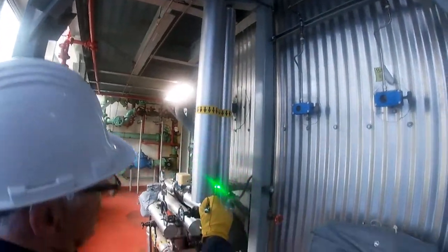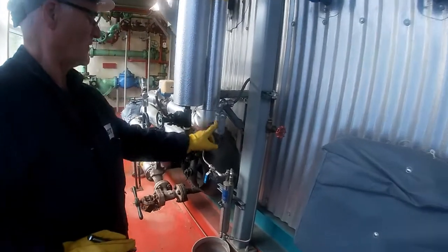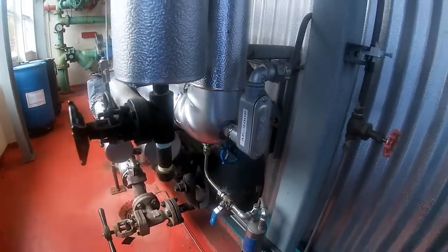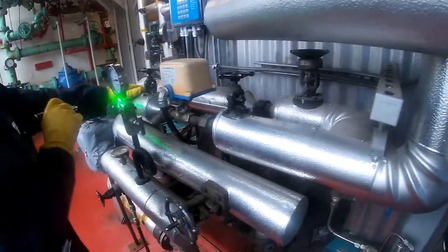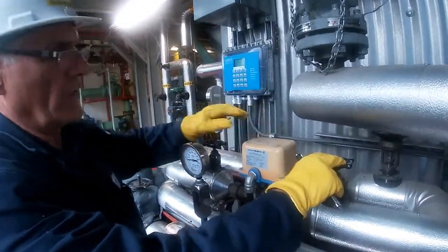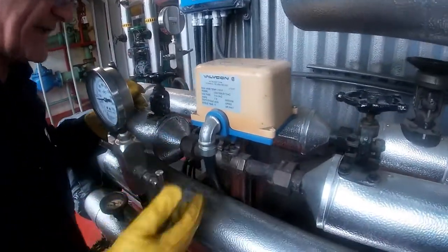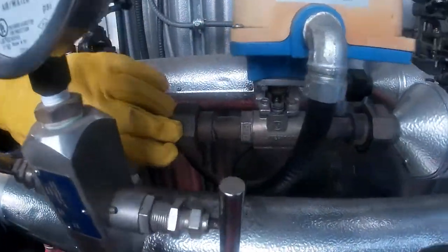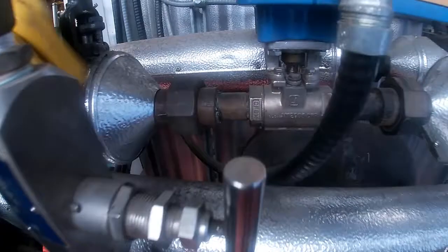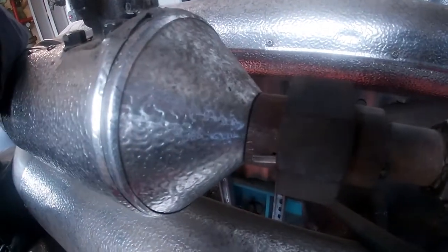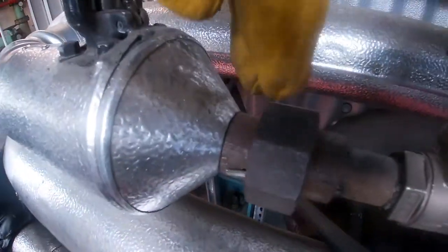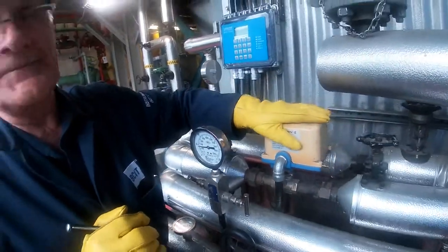The blowdown comes to this conductivity sensor, which measures the conductivity of the water that's coming out of the blowdown. From there, we go through these 2 hand valves to this control valve, and in fact, it's hard to see, but there's actually an orifice in here which limits the amount of flow. And that little tiny tab that's sticking out of the end of that union actually holds on to the little orifice plate. Okay, so that guy right there is controlling the flow rate. This is just an on-off valve.